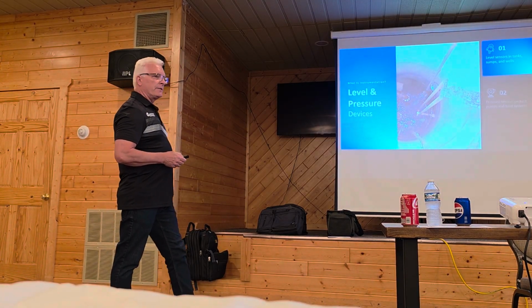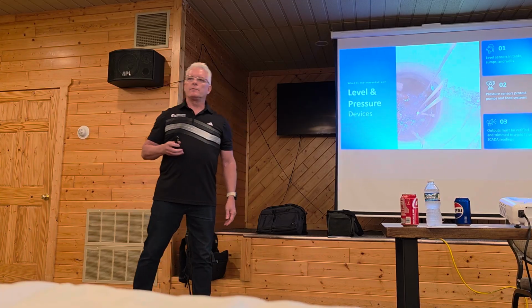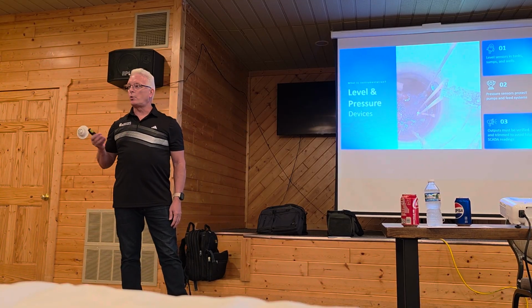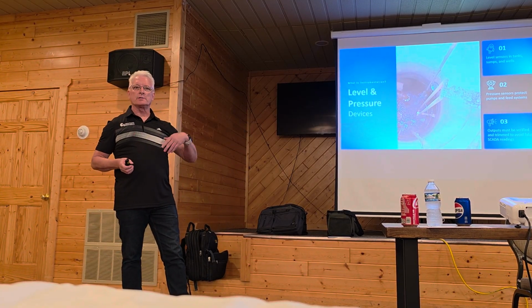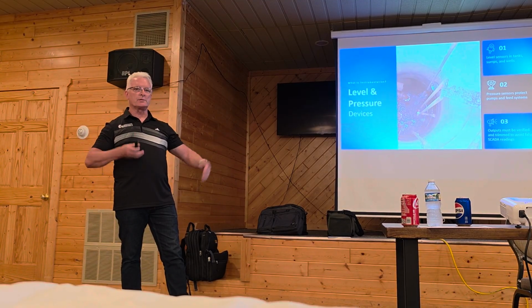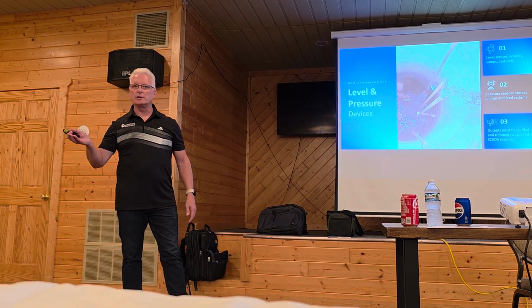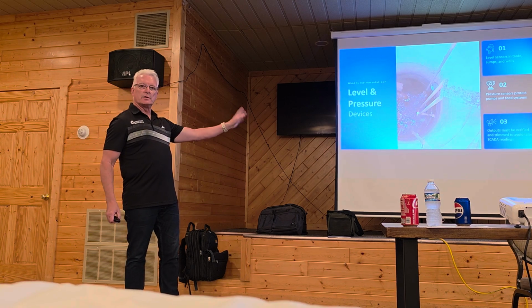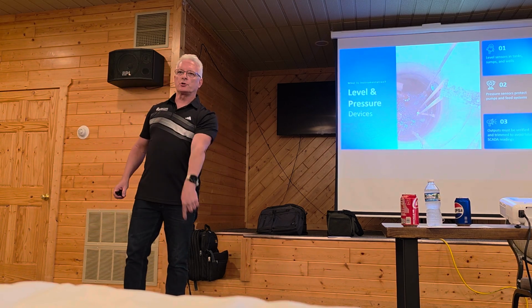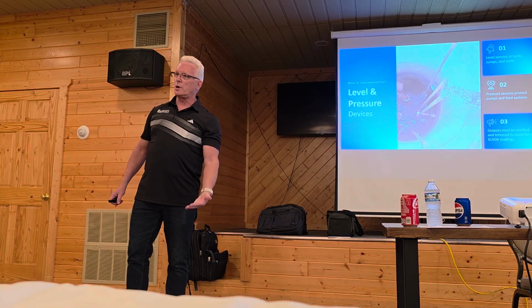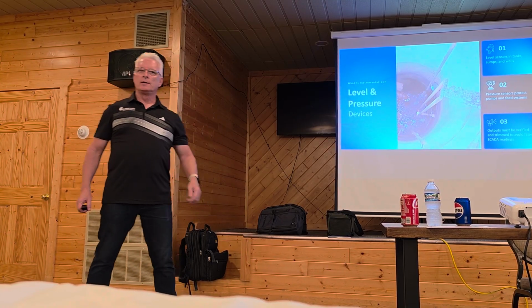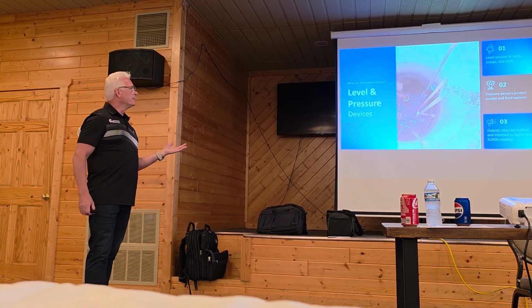So level and pressure devices, you have pressure on your water towers that tell you the level on your water towers, and then you set your start-stop points to fill the tower and tell your pumps to start. You have pressure transducers in the lift station that are submersible, so they're down below and they're telling you how much water is on top of the transducer, and then that tells the pumps to start and stop.